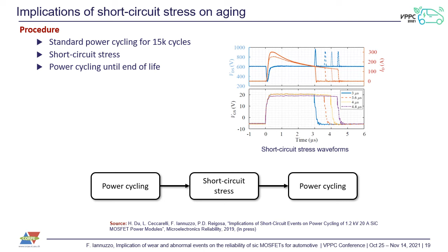You can see the power cycling temperature before and after short circuit. The blue one is zero number of cycles, and the red, orange and yellow ones are the power cycling temperature right before and right after the short circuit. In this case, it's 50 repetitions of short circuit, just to emphasize the effect. But later on, we did it also with a very limited number of repetitions, 1 or 2, at 60 and 100K. You can see that right after the short circuit event there is a significant jump in temperature swing between the orange one and the yellow one.